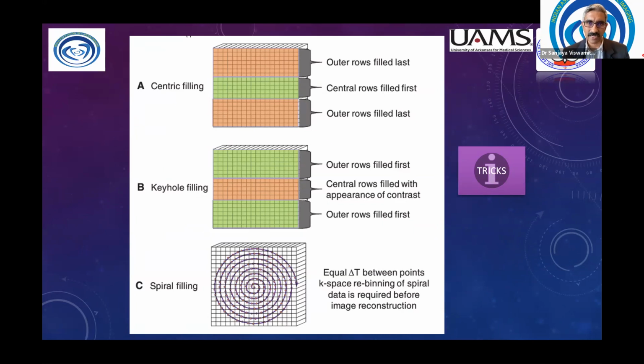Now imagine what happens, right? So we said already that the speed of an acquisition, simply put on MRI, is TR, the repetition time, multiplied by the number of phase encoding steps. So here, if you're sharing the outer areas of the phase encoding steps, then you're never repeating this. All you're acquiring is only the central number of lines of K-space, which may be about 30, 40, maybe 50. Hence, the repeated images are going to be much faster than the initial first image, where you took all the lines of K-space and then you're sharing different data across.